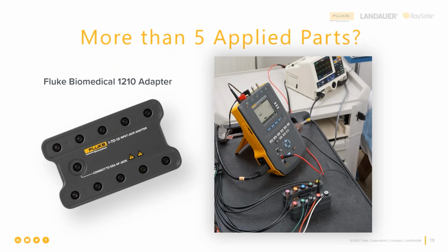Okay, now you have to remember, everything we connect to this 1 to 10 adapter gets shorted together and treated as just one patient connection. And that comes off and connects to the top of the safety analyzer to those lead posts. So we don't run ECG simulations through this, all right, just so you're aware. But it is for electrical safety testing, and it's very handy.